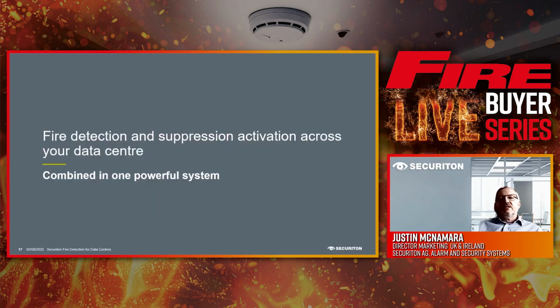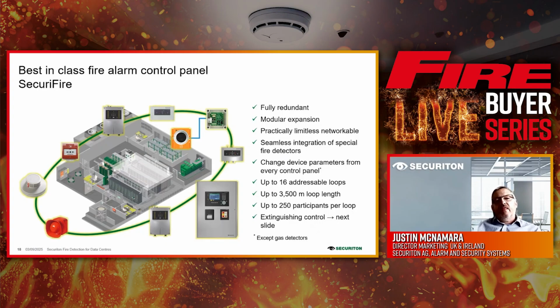I'm going to talk a little bit about the fire panel. We have what we describe as a best-in-class fire alarm control panel, a fully redundant system that we can expand pretty much limitlessly. I have a challenge I put to a lot of people to make sure they fully understand just how limitless our network is. We can actually provide a system with up to 250 devices for each loop, up to 16 addressable loops.